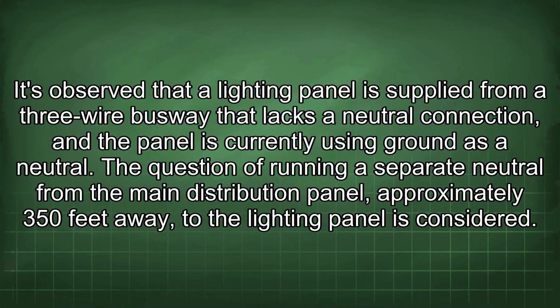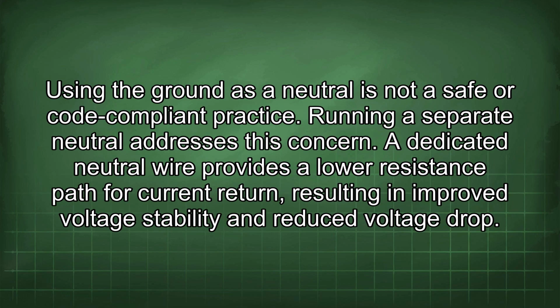It's observed that a lighting panel is supplied from a 3-wire busway that lacks a neutral connection, and the panel is currently using ground as a neutral. The question of running a separate neutral from the main distribution panel, approximately 350 feet away, to the lighting panel is considered. Using the ground as a neutral is not a safe or code-compliant practice. Running a separate neutral addresses this concern.